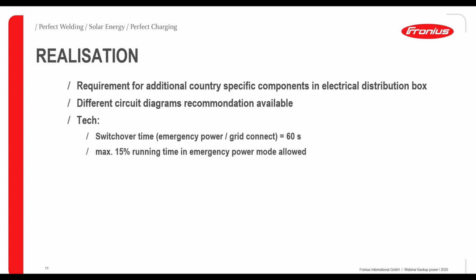There is a switch over time of about 60 seconds. That's important as well. So when we switch over from grid to off-grid mode, there is a 60-second break. So that's something to be known as well. And we have a maximum of 15% running time in emergency power mode per year. So we can double check this.